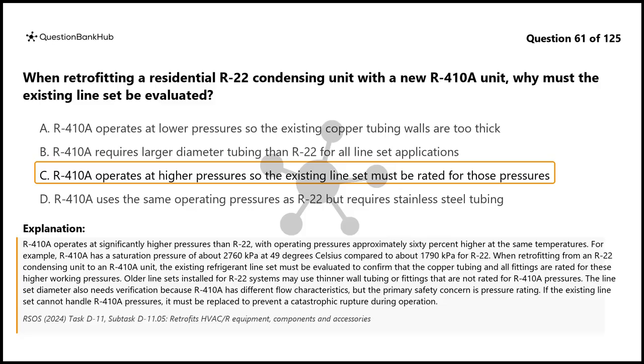Older line sets installed for R22 systems may use thinner wall tubing or fittings that are not rated for R410A pressures. The line set diameter also needs verification because R410A has different flow characteristics, but the primary safety concern is pressure rating. If the existing line set cannot handle R410A pressures, it must be replaced to prevent a catastrophic rupture during operation.